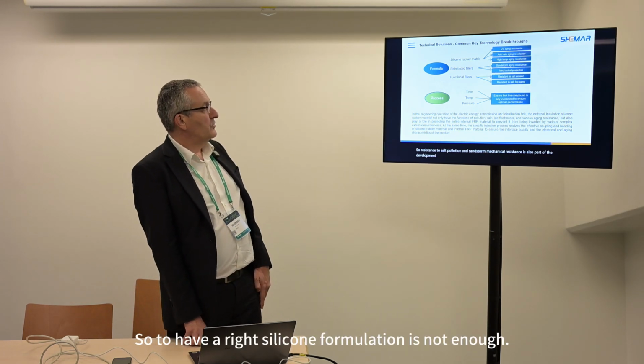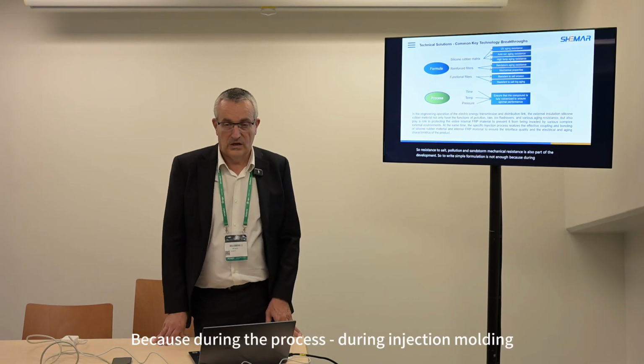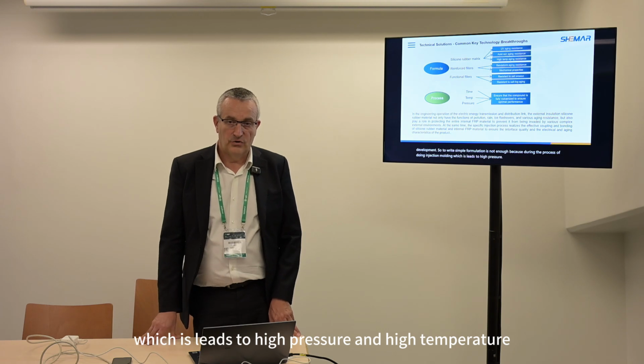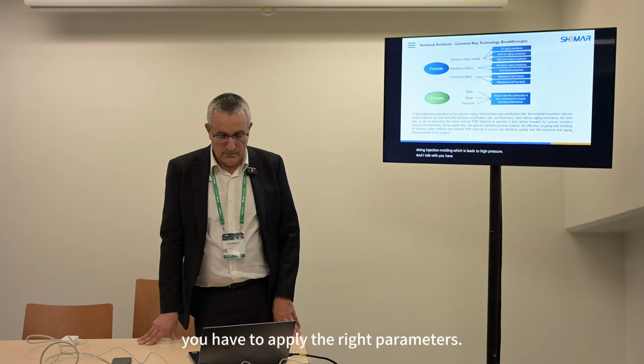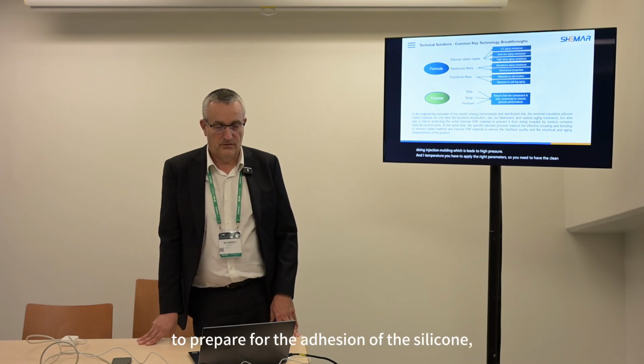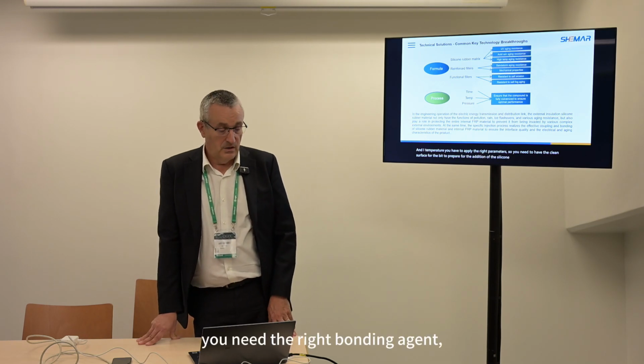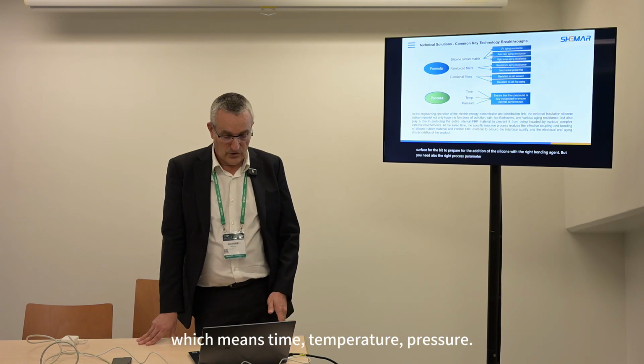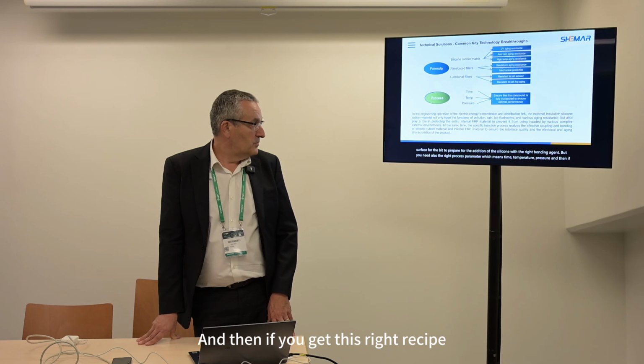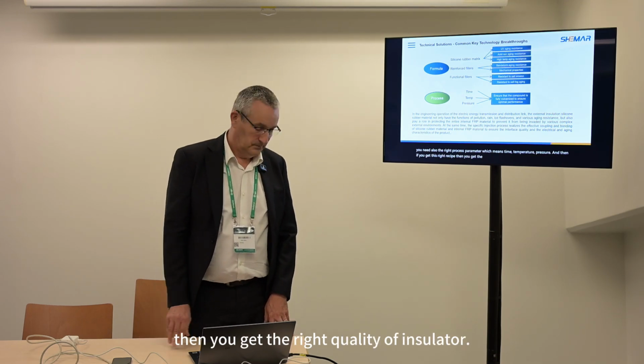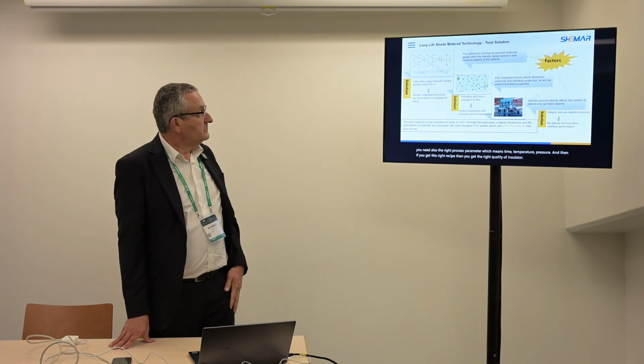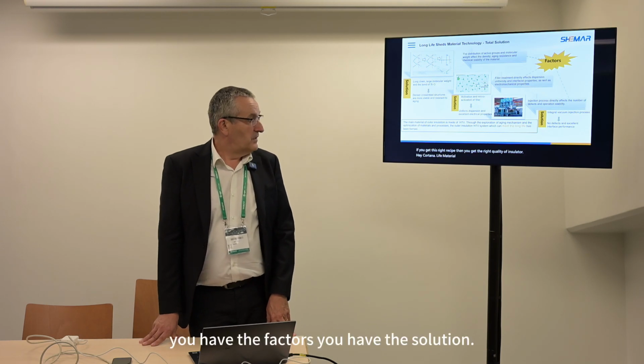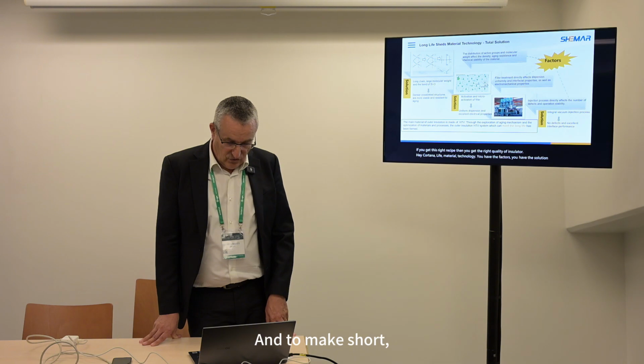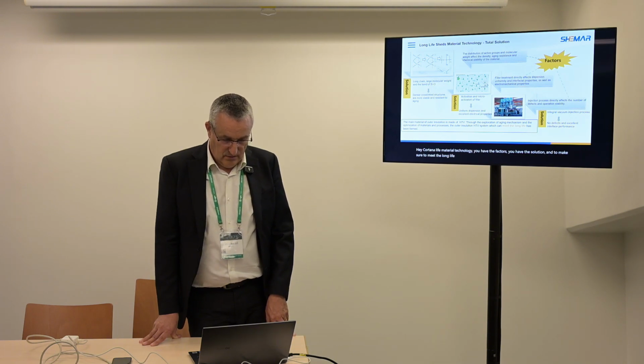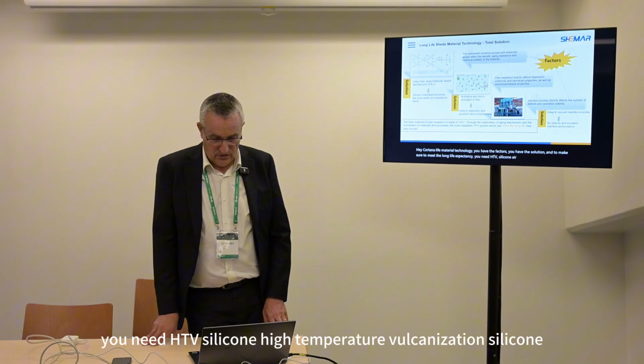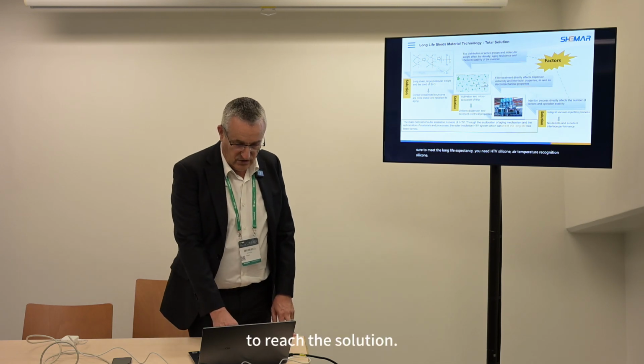To have the right silicone formulation is not enough, because during the process, during injection molding, which leads to high pressure and high temperature, you have to apply the right parameters. You need a clean surface prepared for the adhesion of the silicone. You need the right bonding agent, but also the right process parameters, which means time, temperature, pressure, and then if you get this right recipe, you get the right quality of insulator. So for long-life material technology, you have the factors, you have the solution, and to make it short, to meet the long life expectancy you need HTV silicone, high temperature vulcanization silicone, to reach the solution.